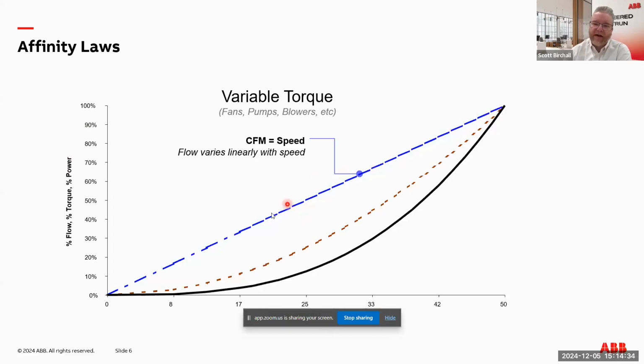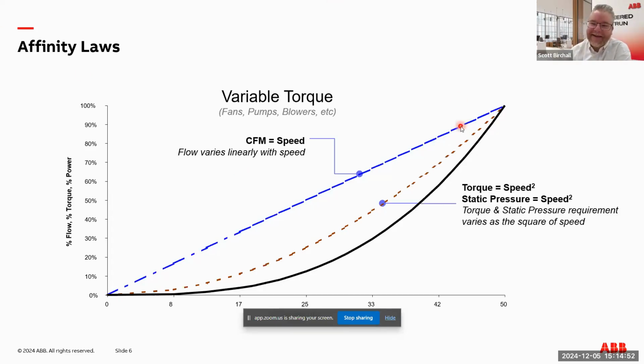So if I'm going with respect to speed, if I cut my speed in half, my CFM is also in half. I suppose I should have changed this to something other than cubic feet per minute for this presentation, shouldn't I? So you're seeing the American, yes, I let that one slip by there. Next one is the torque. Your torque, and also pressure, is proportional to the square of the speed. And then what's really important for this conversation, energy saving, is your power as far as the affinity laws. So your power is proportional to the cube of the speed.